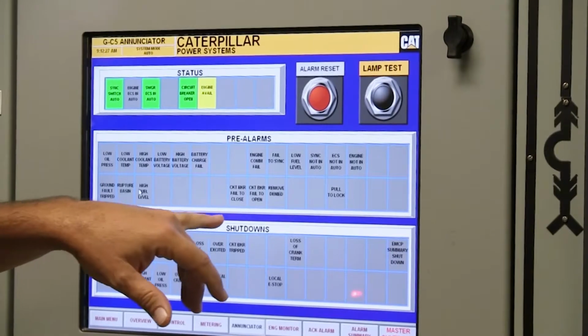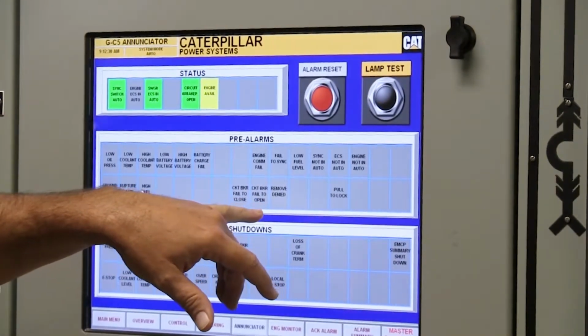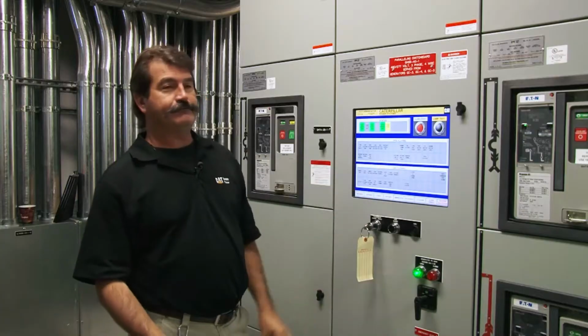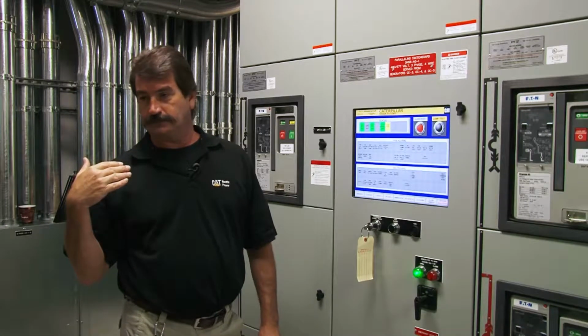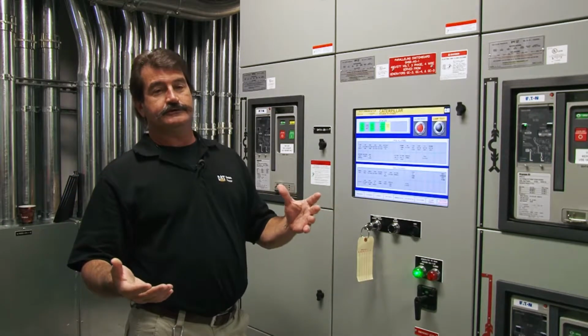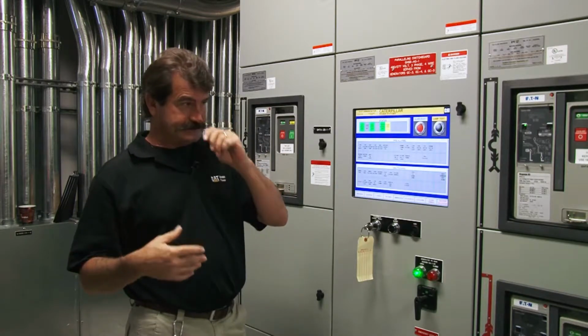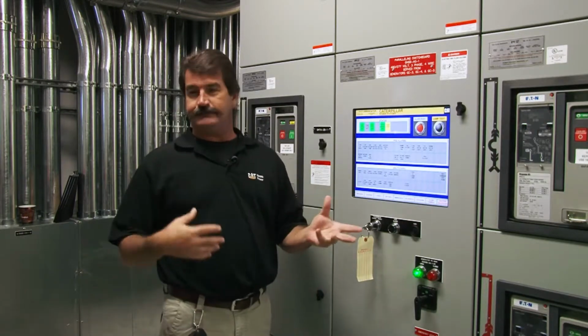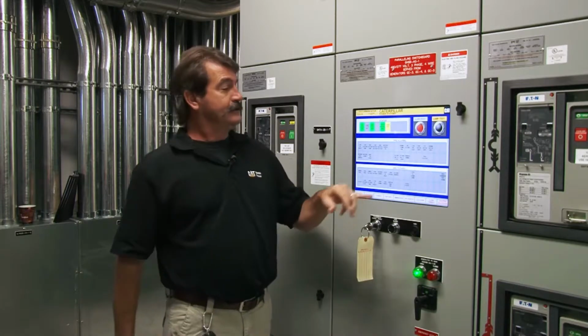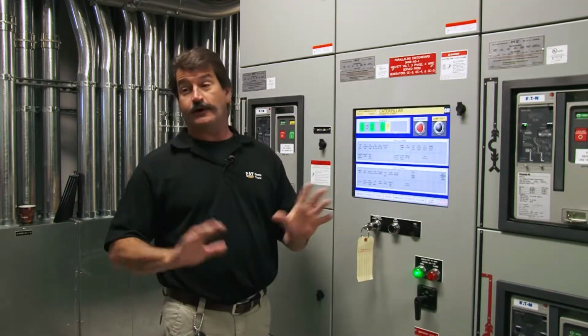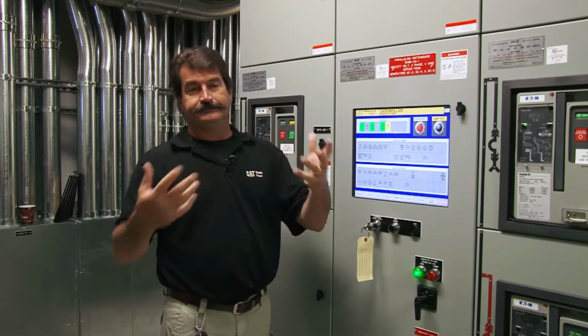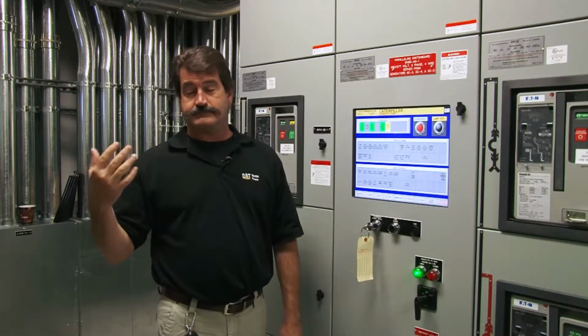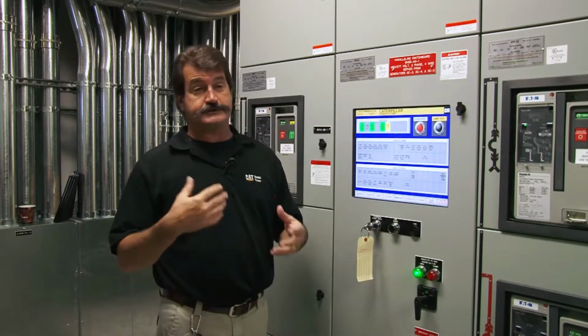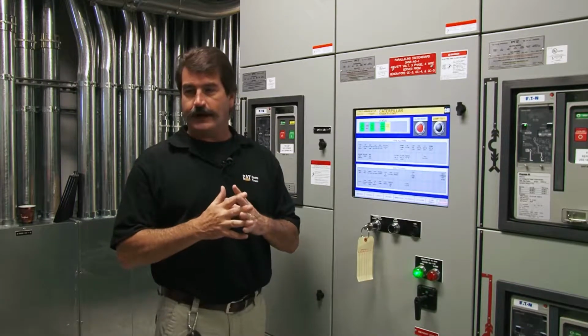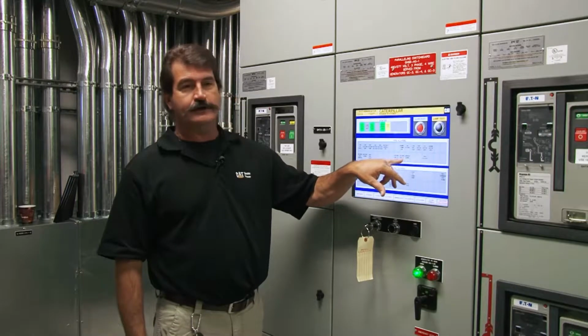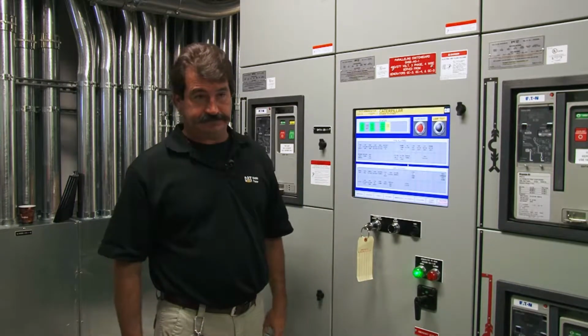High fuel level, circuit breaker failed to close, failed to open, and remove denied. If you're trying to take a gen off, because you have gen demand on, that says you're running 5 gens and you don't need 5 gens, it's trying to take a gen off. If for some reason we say, no, we're not going to take that gen off because you either have too much load or something that it senses is not right, it's going to say remove denied. That's what that remove is, gen demand.